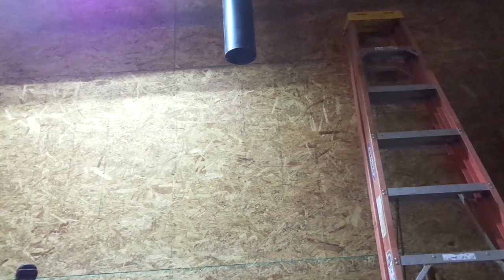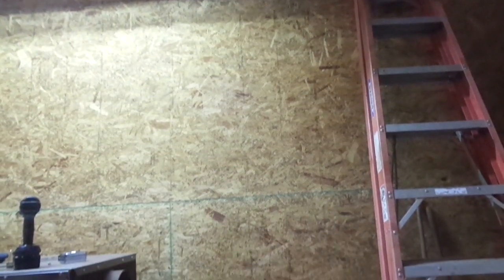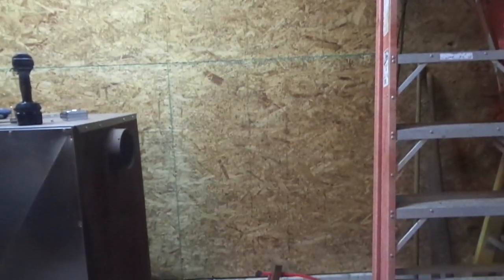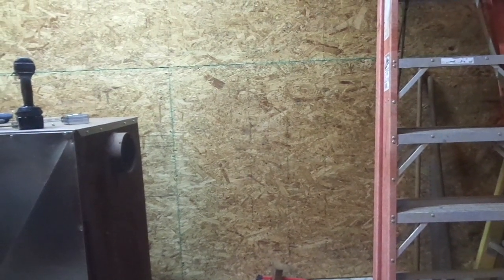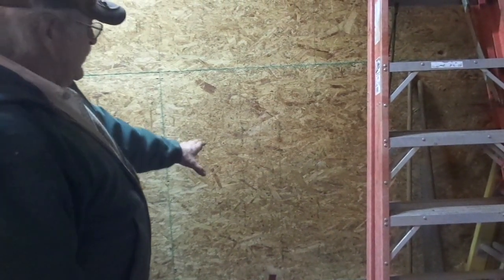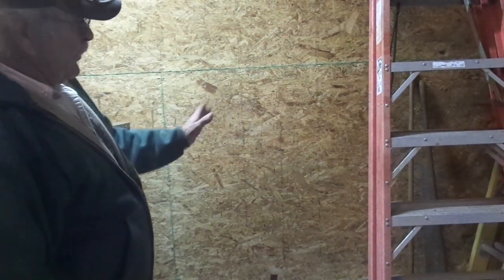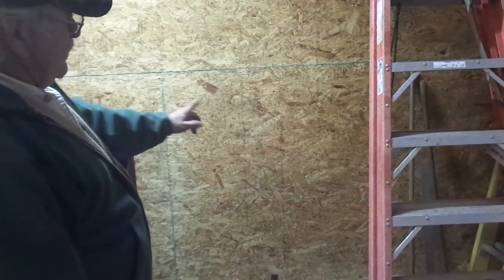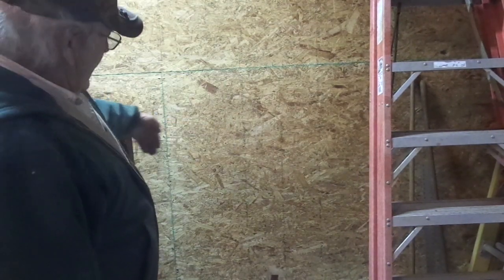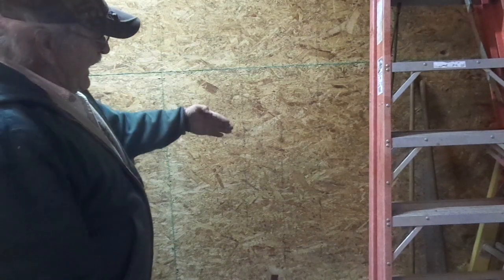But normally what I would do is this would set just a few inches behind the furnace, and this would drop straight down to the point at which it enters into the back of the furnace, right here. This would be right over here, the length of a 6-inch radius, or roughly 9 inches on center from the center line of the flue drop, and then that would go into a clean-out T.